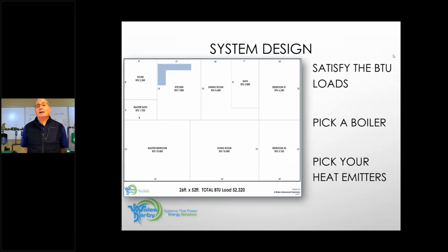My home is a perfect example of that. My home was oversized dramatically based on the heat loss of my house, which I did 3 times. I only needed 57,000 BTUs to heat my home. And I had a 130,000 BTU net boiler heating my home. And I also had 101,540, if I do recall, amount of baseboard installed in my house at 180 degrees.